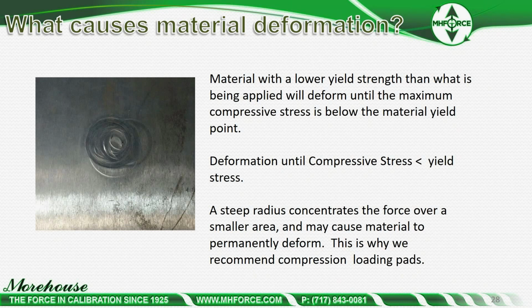Material with a lower yield strength than what is being applied will deform until the maximum compressive stress is below the material yield point. So basically, deformation until compressive stress is less than the yield stress. A steep radius concentrates the force over a smaller area and may cause material to permanently deform. This is why we recommend compression loading pads.